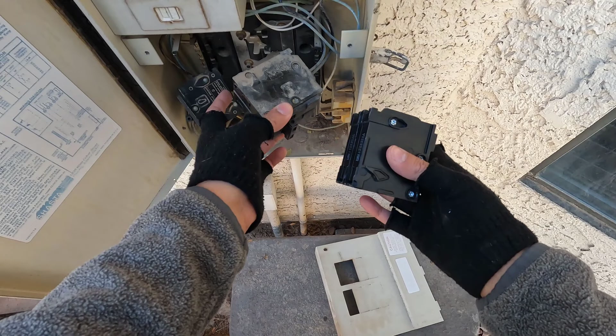This company initially, it's like ETA or ETI or whatever, got bought out by Siemens, so the design is a little bit different. However, these are both 15 circuit or 15 amp circuit breakers, or dual 15 amp circuit breakers. So we've got a combined 30 right here, and then another 15 right here, for a total of 45 amps. And the main panel, this is all connected to a 50 amp breaker.